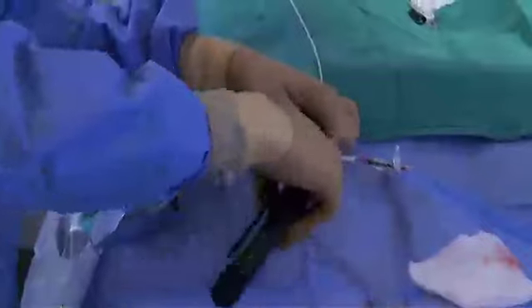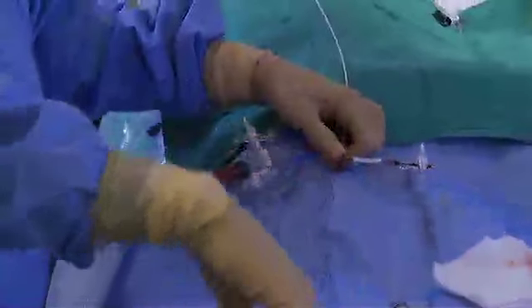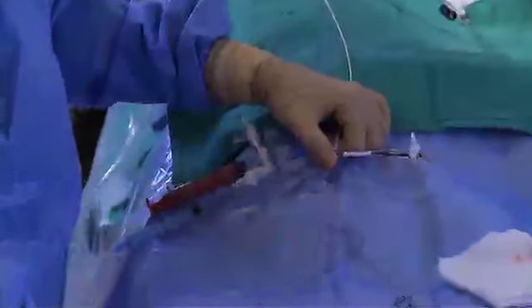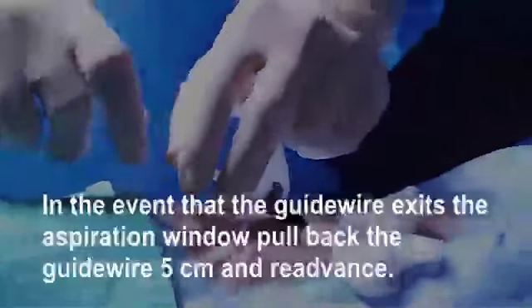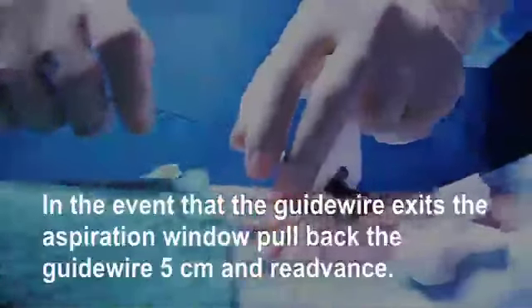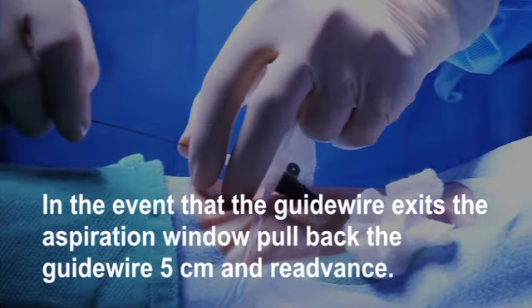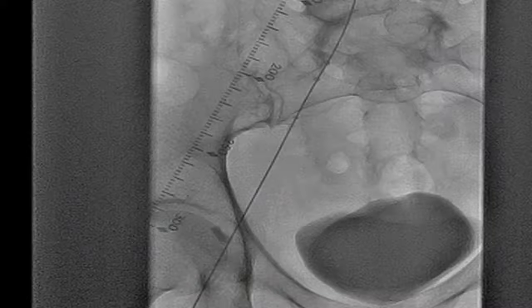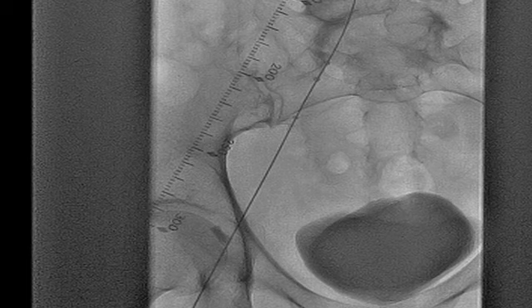Turn off the ODU and remove the dispersion wire by releasing the luer lock located at the base of the ODU and pulling the dispersion wire out of the catheter. Under fluoroscopy, replace the dispersion wire with a 0.035-inch guide wire. In the unlikely event that the guide wire exits the aspiration window, pull back the wire about 5 centimeters and re-advance. Verify that both balloons have been completely deflated.